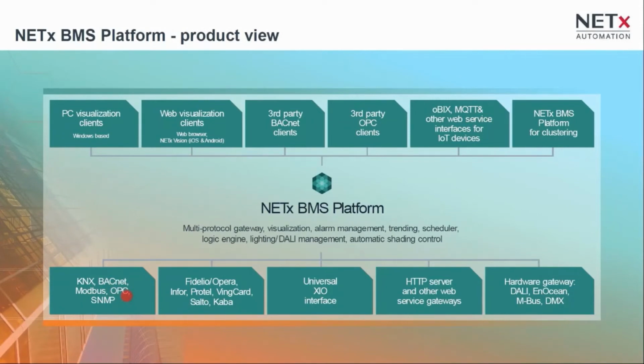This may be an OPC-DA or OPC-UA server for a fire alarm system, for an elevator, whatever you have there. So this is extending the type and number of protocols. For hotel projects, you will find typical hotel property management and door access systems. You may connect HTTP servers to receive web content as well. You may connect hardware gateways like a KNX DALI gateway.